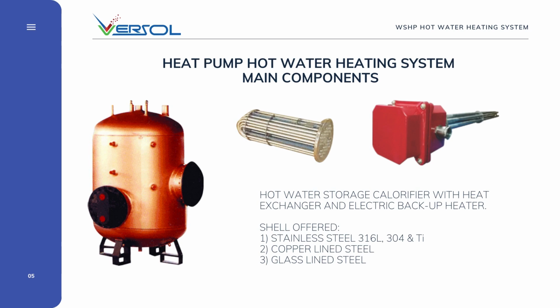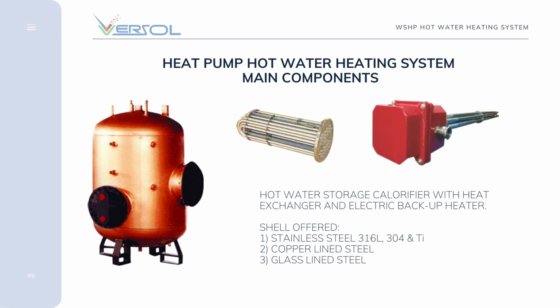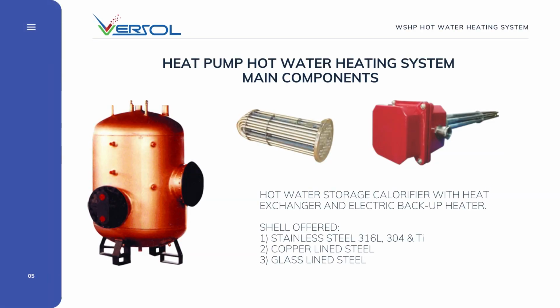Versotherm, the storage unit, is a major component of the system, which stores the heat energy. Versotherm units are manufactured in Versol facilities in the UK, Poland or Italy. Versol offers a different range of calorifiers based on the requirement. Versotherm selection is based on the heating source or heat exchanger type and the material of construction. For a heat pump water heating system, the calorifier tank can be Versotherm STIUT, with a U-tube bundle heat exchanger, or Versotherm STI Spira, with a spiral tube heat exchanger. Based on material of construction, Versol can manufacture calorifiers in three ranges: copper lined steel, stainless steel or glass lined steel.